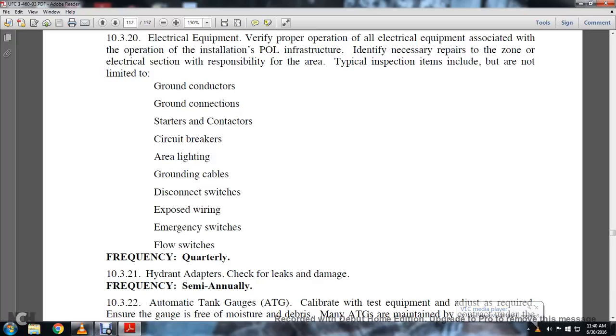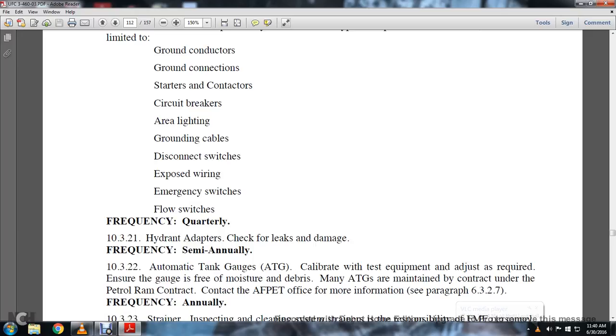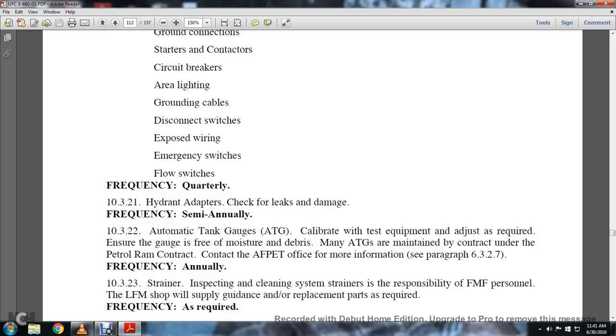Hydrant adapters. Check for leaks and damage semi-annually. Automatic tank gauges. Calibrate with the test equipment and adjust as required to ensure the gauge is free of moisture and debris. The automatic tank gauges are maintained under the Petrol Ram Contract. Contact the AFPET office for information. See paragraph 6.3.2.7. Frequency: annually.